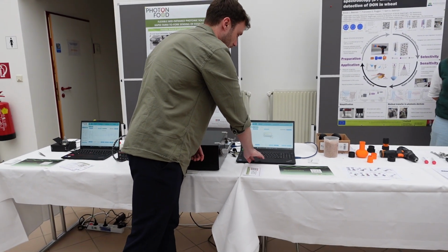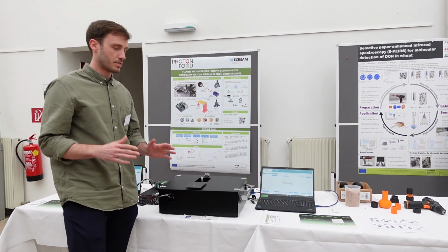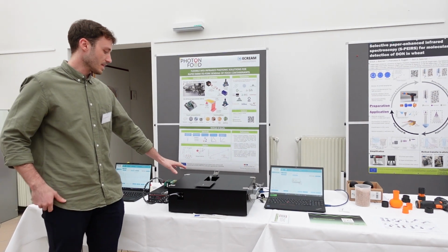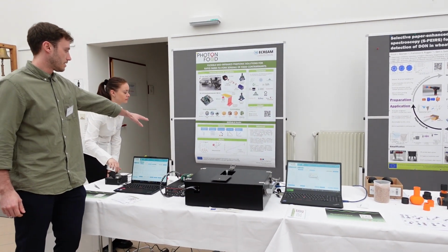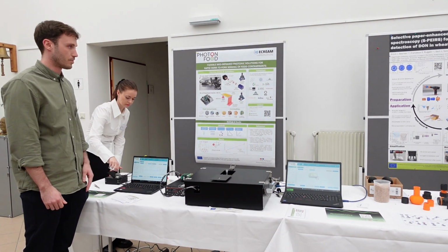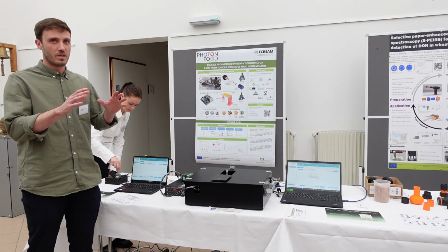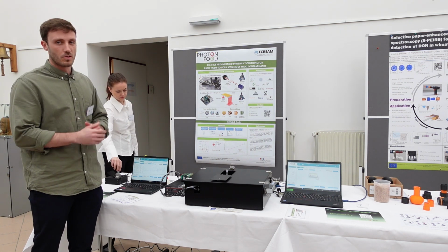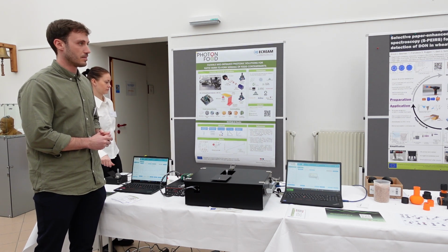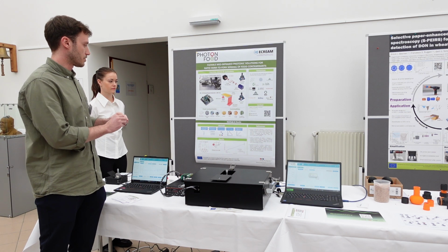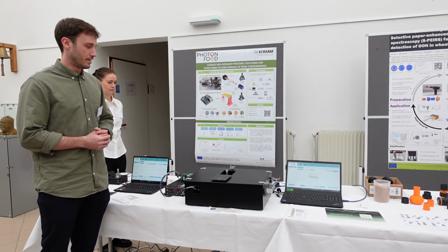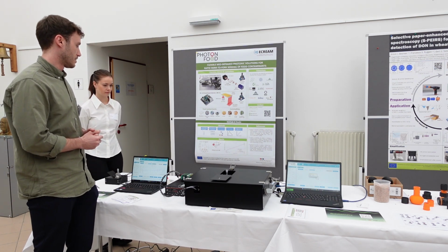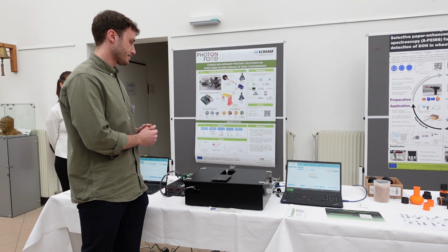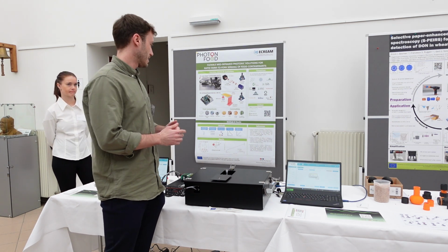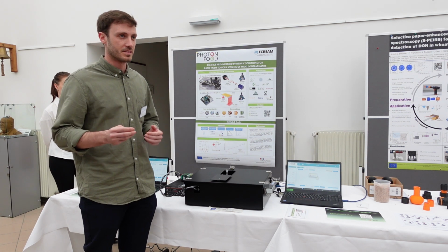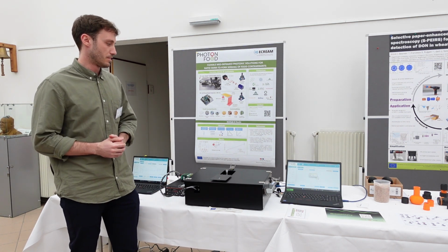You also record the background before, and it takes around 3.5 minutes to record the whole spectra, as it is a tunable laser. It is tuning around these wavelengths, as you see here. The range is between 1700 and 1640 in wave numbers, and this was developed according to the main DON carbonyl group, so that we have data points at 1682 or 83 inverse centimeters, so that we can detect DON directly on paper thanks to these data points. Here the laser is tuned by a programmed lookup table, introducing different currents and temperatures, which helps the tuning of the laser.